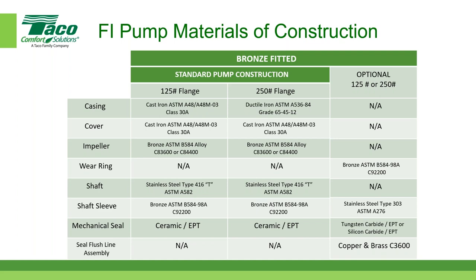The shaft is stainless steel, pretty straightforward for both sides there. It's a pretty robust, heavy duty shaft. The shaft sleeve actually goes onto the shaft, and that's where the impeller gets put on. Standard is bronze, and some folks in their specs require stainless steel, so you can get a stainless steel one. I personally would recommend staying with the bronze because it's a lot easier.